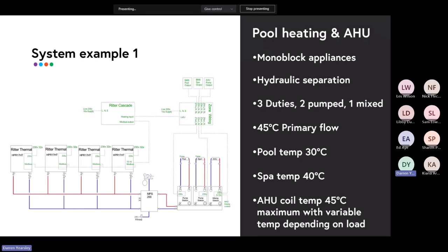Okay, so here's an example of a system which we did for an aged care application. It was a pool heating application where they had an indoor pool, a spa pool, and an air handler. The key metric for them was to reduce carbon, and all of it was run on gas. So we replaced the gas appliances with an array of 4 heat pumps. So we've got 80 kilowatt input, and you can see it's hydraulically separated. The heat pumps connect to the buffer, and then the buffer connects to the pump stations and the mixing station. And so I think this system we ran at a 45-degree flow temperature.